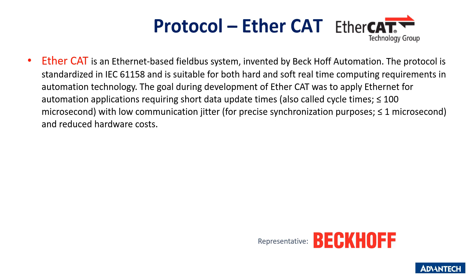EtherCAT is an Ethernet-based field bus system invented by Beckhoff Automation. Short cycle times can be achieved since the host microprocessors in slave devices are not involved in processing Ethernet packets to transfer process images — all process data communication is handled in the slave controller hardware. This makes EtherCAT a high-performance distributed I/O system. Process data exchange with 1,000 distributed digital I/Os takes about 30 microseconds, typical for a transfer of 125 bytes over 100 Mbit/s Ethernet. Data for and from 100 servo axes can be updated at up to 10 kHz.